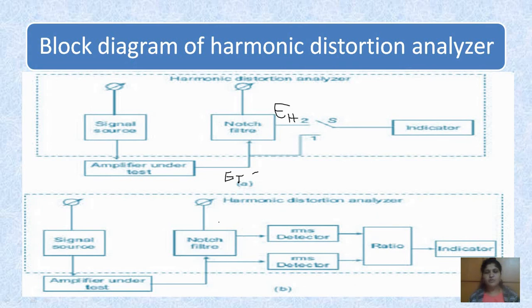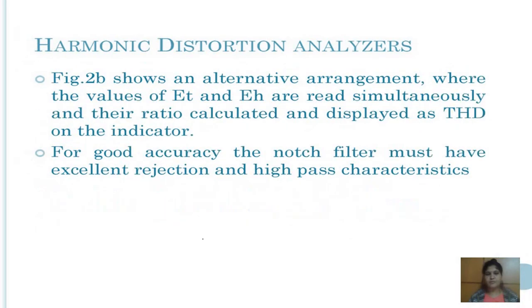The notch filter removes the fundamental component from the signal, giving good accuracy and excellent rejection, and it has high pass characteristics. It should attenuate the fundamental by 100 dB or more, and attenuate harmonics by less than 1 dB. The filter also needs to be accurately tuned to the fundamental of the signal source. In the second figure, ET and EH are read simultaneously, their ratio is calculated, and the result is displayed as total harmonic distortion on the indicator.